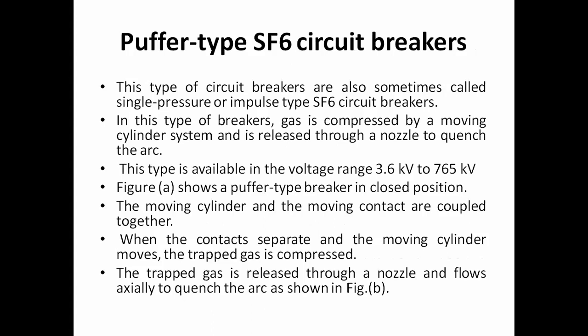Now, the puffer type SF6 circuit breaker is also sometimes called a single pressure or impulse type circuit breaker. In this type of circuit breaker, gas is compressed by a moving cylinder, and it is released through a nozzle to quench the arc.